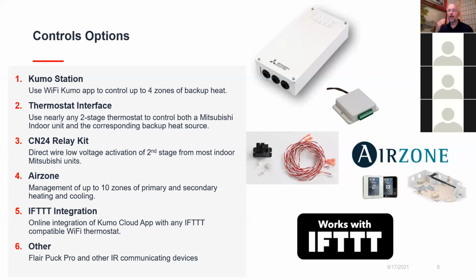Other ways of approaching it, we know that one of the more popular methods for doing integrated controls in Massachusetts, particularly when it's not a Mitsubishi equipment that has all these other options, is a Flair Puck Pro, which uses the same IR communication methodology as a remote control to communicate with indoor units.